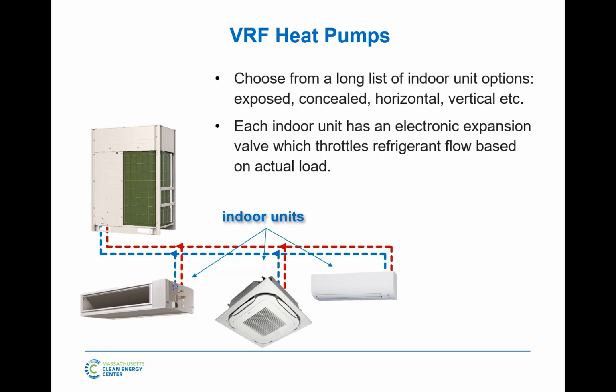So this unit knows exactly at any point in time how much heating or how much cooling that room wants, and it throttles that valve open and close. So it might say, I'm only 20% open, 40%, 60%. So you kind of run these. Usually the air runs all the time. You're just always rolling that fan, but the expansion valve decides how much heat or how much cooling you get. And each of these fan coils or indoor unit does the same thing. They each have their own controller, their own thermostats, and they each decide, do I want more cooling or do I want less cooling? That's the variability of these systems.